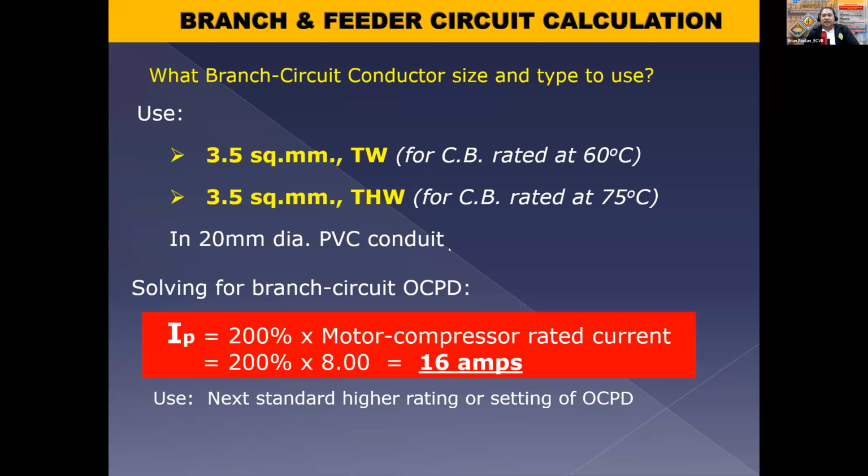Yung kuan sir, kung mas maliit, talagang yung biggest kasi yung circuit yung sinize up natin sir, no? Yung full load ampere nameplate, ang protection sa motor niyan is yung overload relay niya, no? Ang sa circuit breaker natin is protection ng circuit natin including conductors from short circuit and ground fault na.